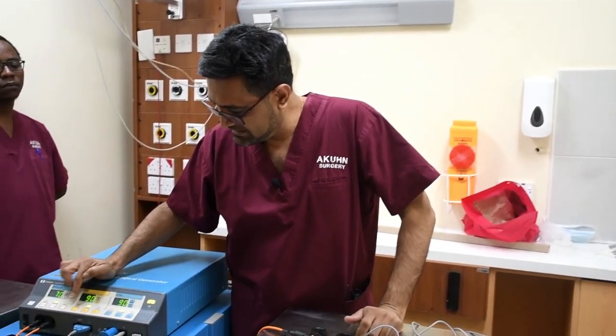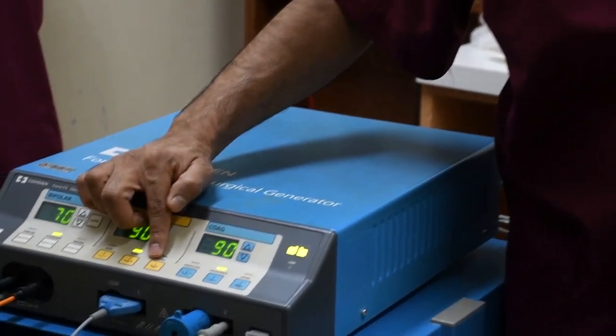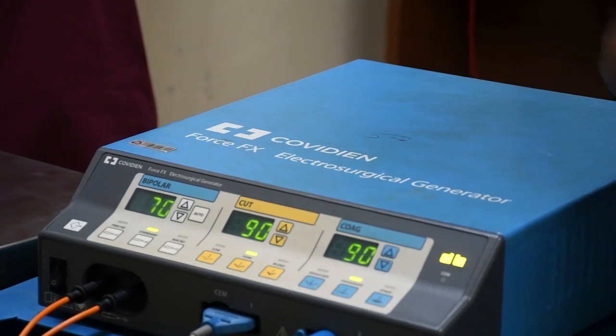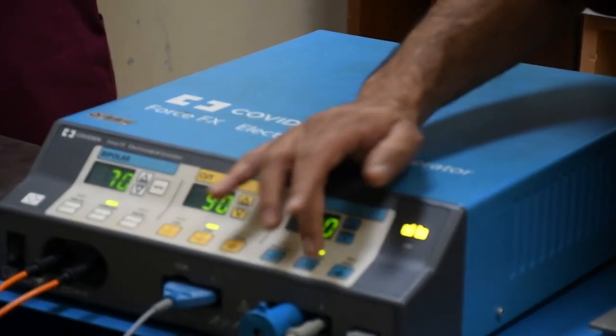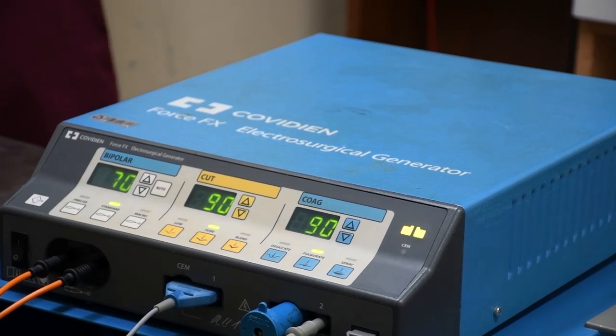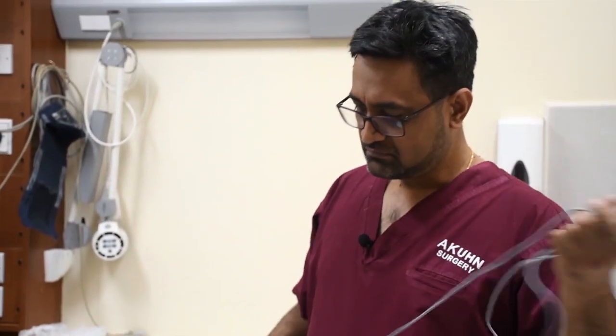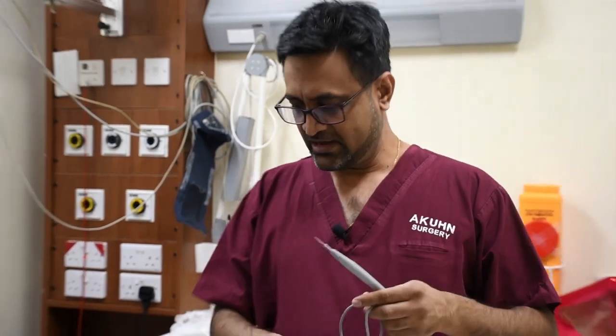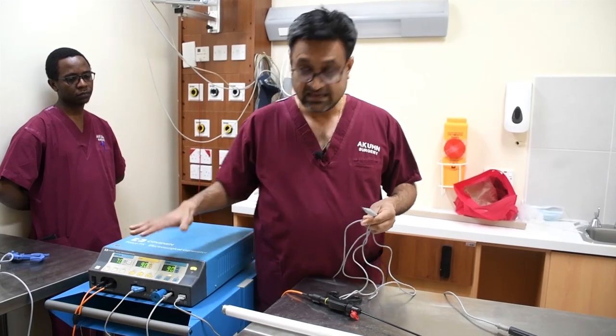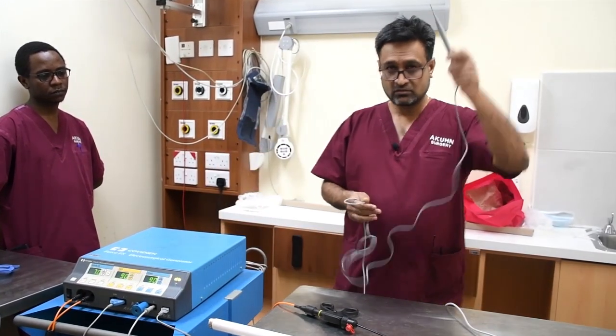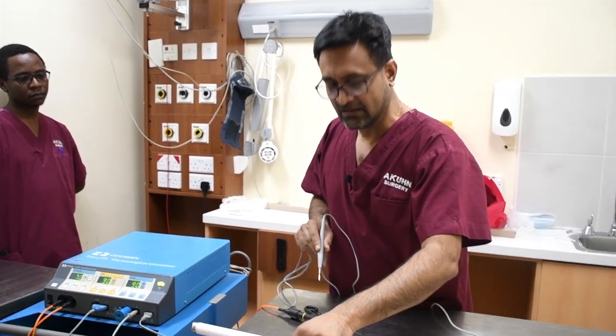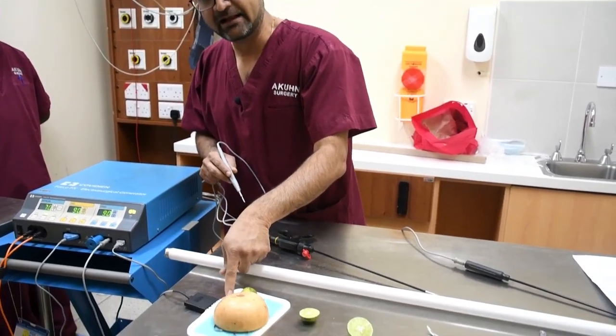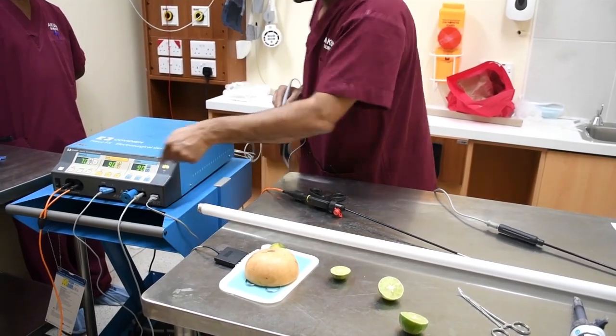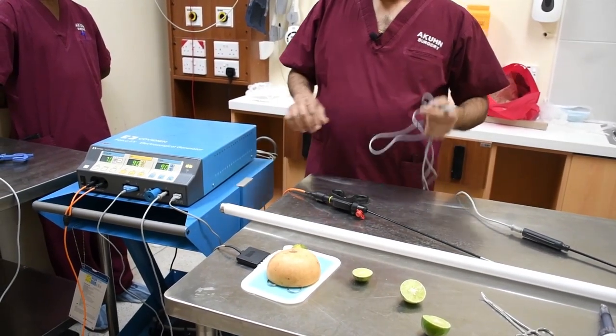Then we will go into what these mean: the pure, the blend 1, blend 2, and then there is the coag mode. And in the coag mode, there is desiccate, fulgurate, and spray. We'll have to go into those individually. Now let's go into the circuit. The monopolar circuit is when you have the output from the ESU into the instrument. This is, let's say, our patient. This is a return electrode which takes it back to the machine to complete a circuit.